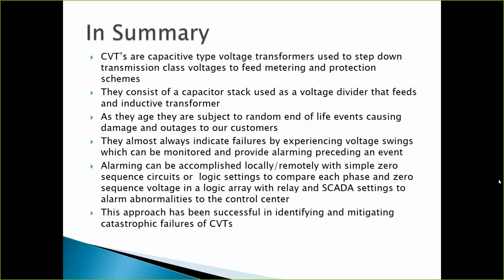But what they've done now, they've gone to a Nomex type paper. It's not even a paper; it's a polymer. So the life expectancy of the CVTs is 20 years. Typically on our system, they're about 25 years, and the drift was a problem in the old days. It's not so much a problem now because they use better quality Nomex paper to make them with. It's a polymer paper. It's not the old cellulose paper. So the accuracy is not a concern over time.